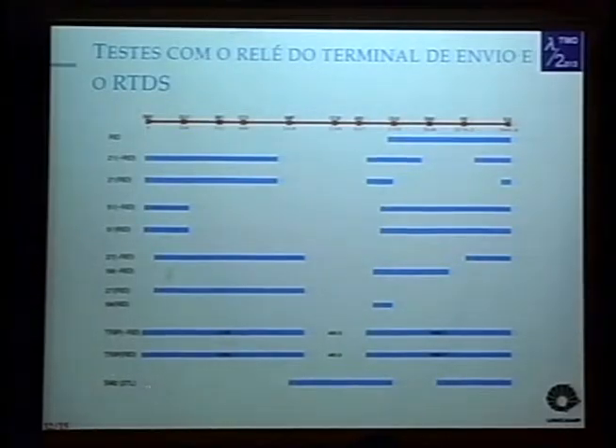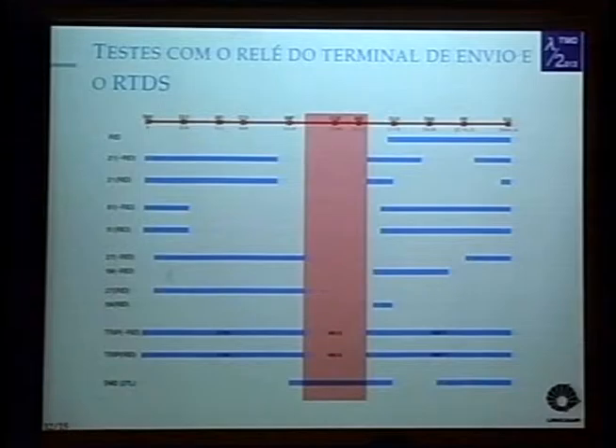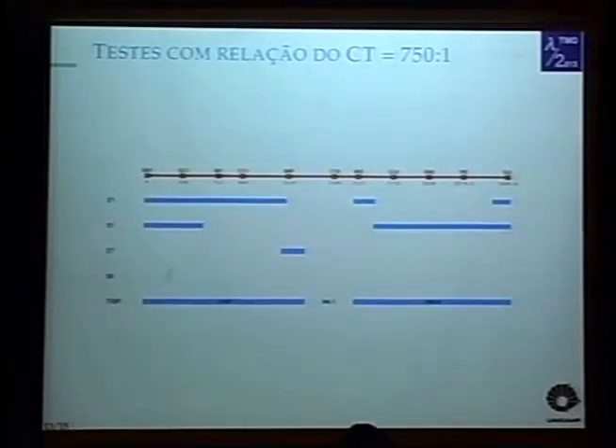So here we included an under voltage relay on the substation of Serra da Mesa 2, because we could have a possible communication with the substation of Serra da Mesa 1, since they are physically close to each other, so it could protect the central segment of the line. We can see that altogether, if you have a relay located in the substation of Serra da Mesa 1, and together with it we use an under voltage relay on the substation of Serra da Mesa 2, we would be able to protect the whole AC link completely in the energization study with non-load.